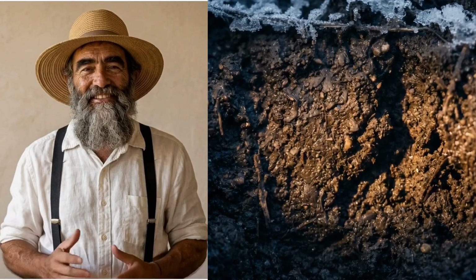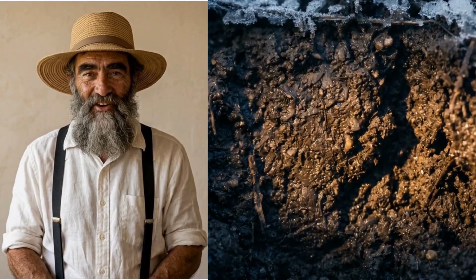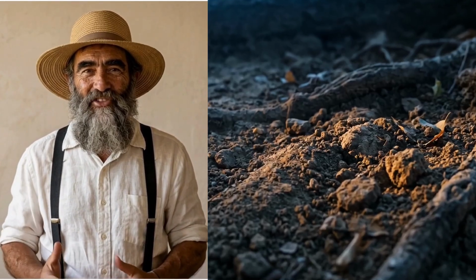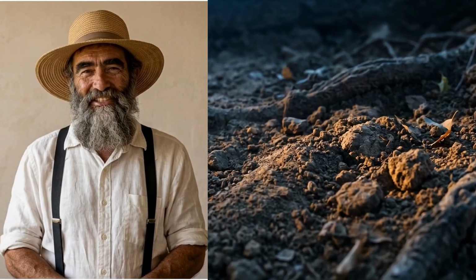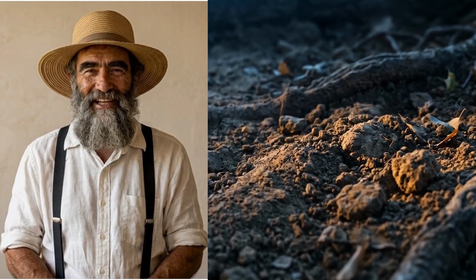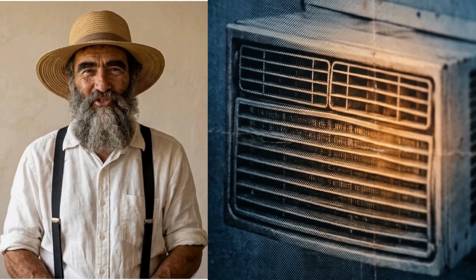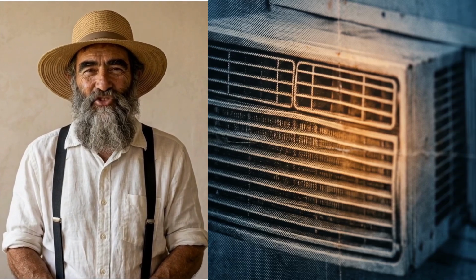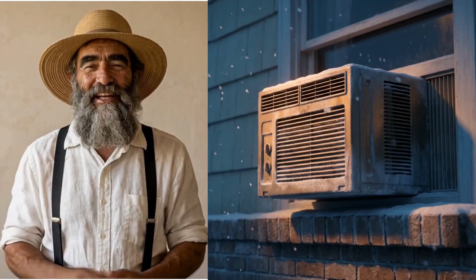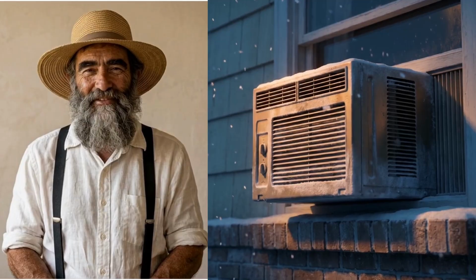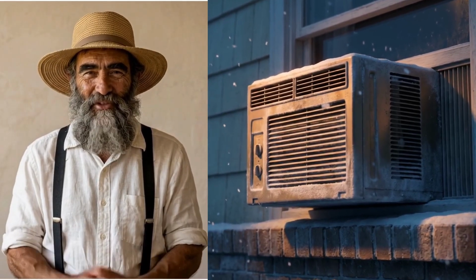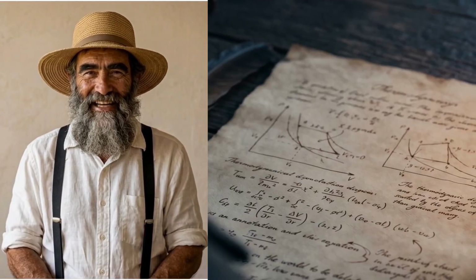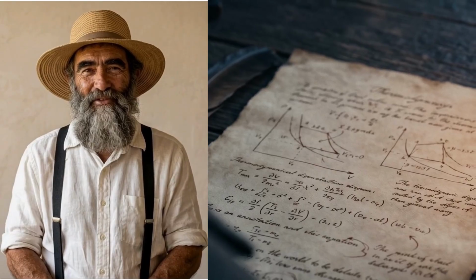The sun heats the surface. Wind and rain and snow move energy in and out of the top few inches of soil. But 6 feet down, the temperature curve flattens. At 10 feet down, in most of the continental United States, the soil temperature is within 5 degrees of the annual average air temperature for that location, and it does not swing more than a few degrees across the entire year. Farmers knew this. They built accordingly.